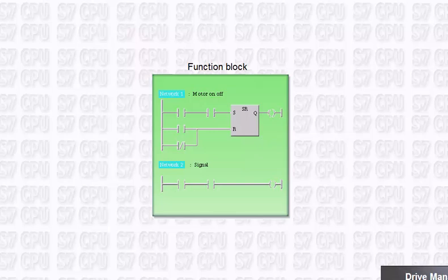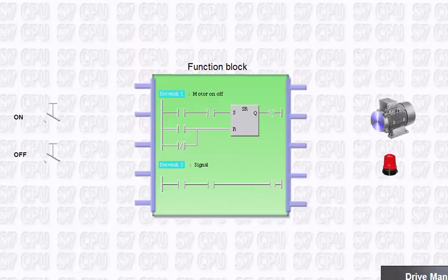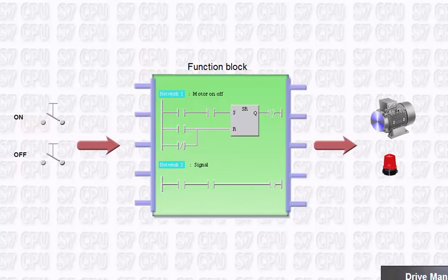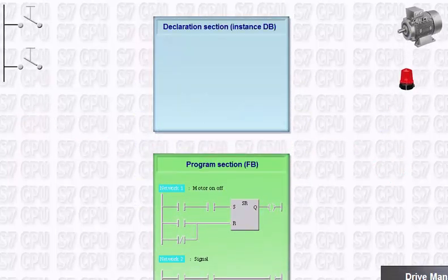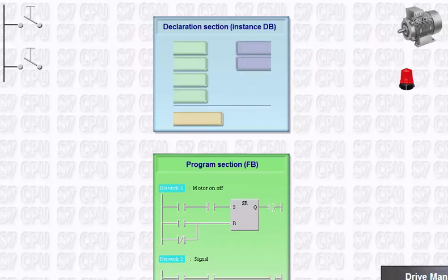A simple user program is used to illustrate how a function block communicates with the various memory areas of the CPU via its parameter interface. The ladder diagram displayed here implements a simple multi-usable motor block. The motor is switched on and off via push button. The on status is additionally displayed via a blinking signal. The block can be used repeatedly for the same motor type. A certain motor is selected merely by assigning the interface.